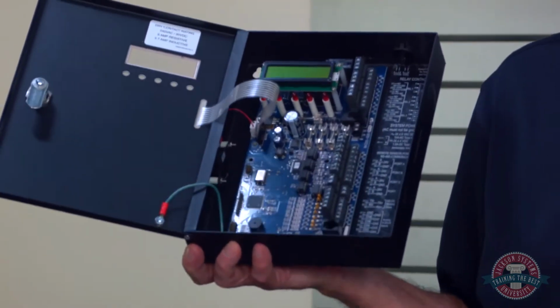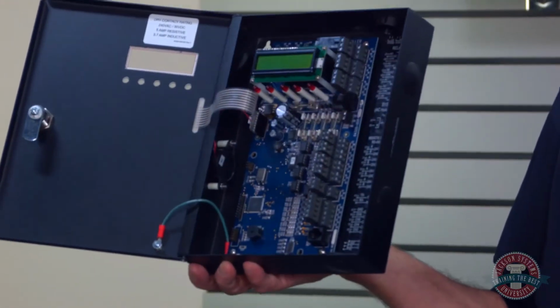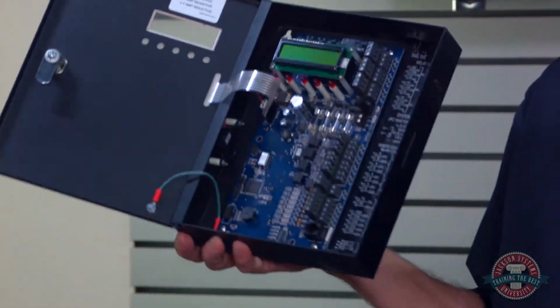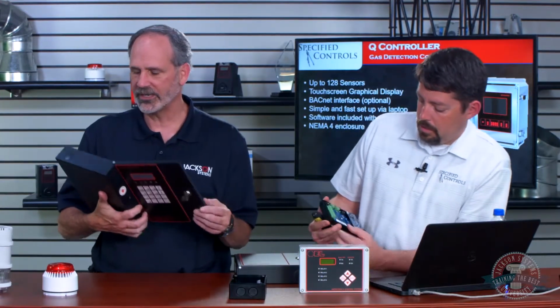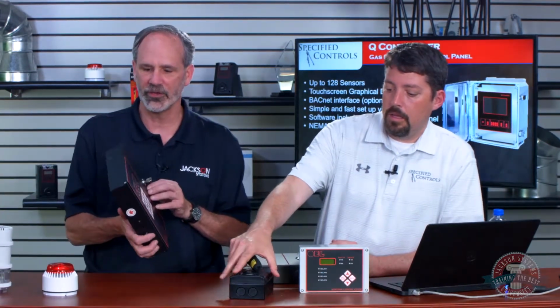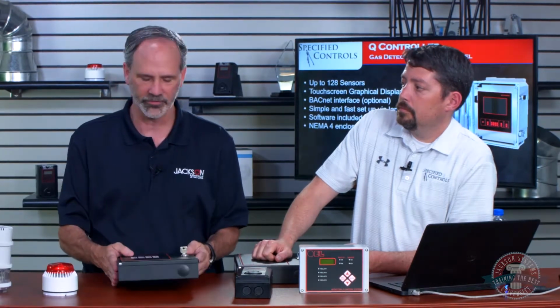I think that's right. When we design a system, we don't ever put 120 volts through them. You can, they're rated for it, but we always pull in a relay or something else. It is a mechanical relay, it's not a triac. And it's Form C, meaning it has normally open and normally closed. So if you want to set it up so that if this panel loses power the fans start, you wire the fans to the normally closed contact, or you can do that at the relay at the motor starter or whatever. So in general, while you can bring 120 volts into it for the relays, we don't. We designed this whole panel to remain low voltage. You're talking about like 24 volts? 24 volts, yeah, low voltage 24.